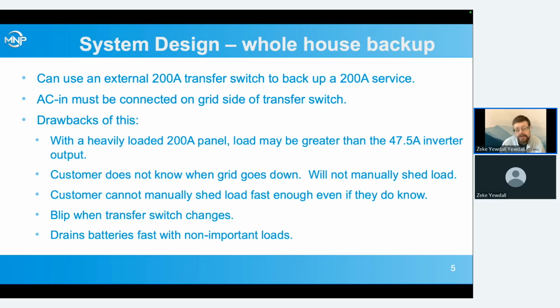There's a lot of drawbacks to doing this. One is that if you have a heavily loaded 200 amp panel and its load is greater than the inverter output at the moment it switches over, your inverter will instantly shut off from an overload. It's not very useful. If you know that the 200 amp load panel on the house is not really heavily loaded and it will be fine on one inverter, you can do it.